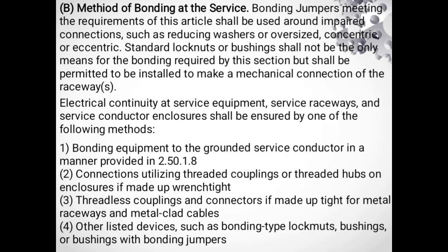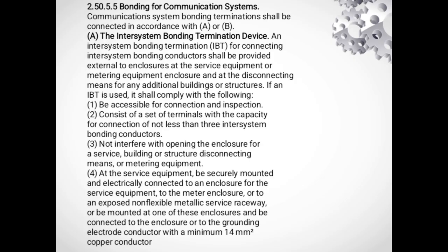Methods of bonding at the service. Section 2.50.5.3 outlines acceptable methods of bonding at the service. Banding jumpers are essential for bypassing any potentially compromised connection. This jumper must be sized appropriately and installed to ensure a reliable electrical connection.